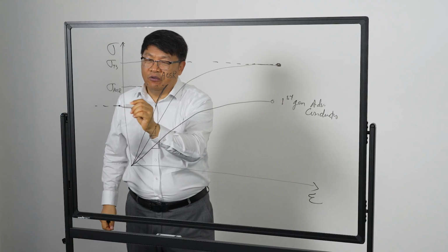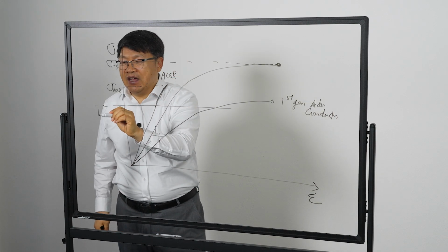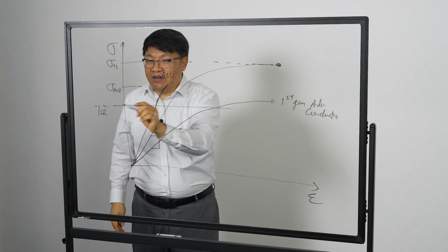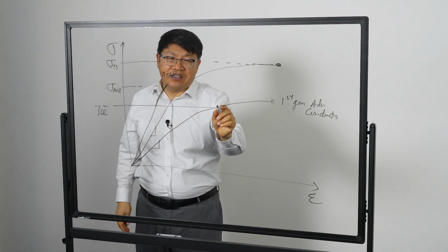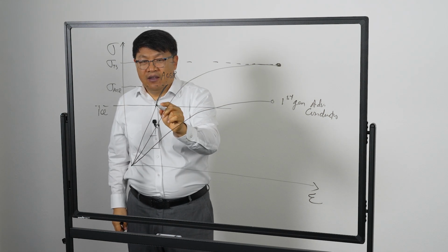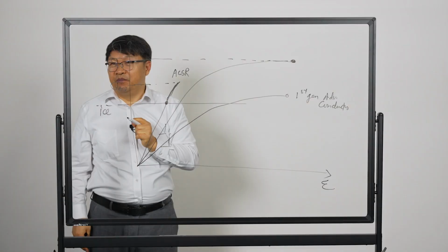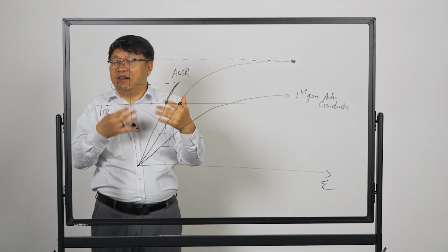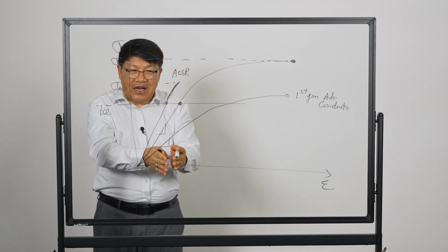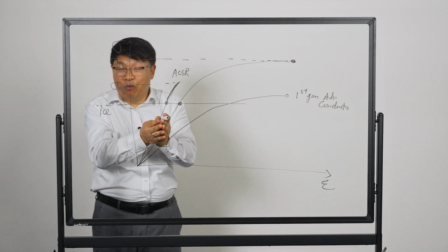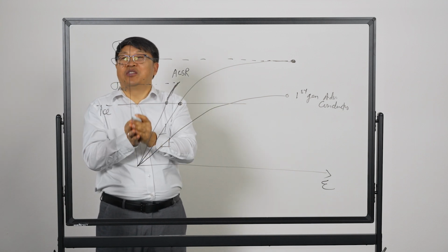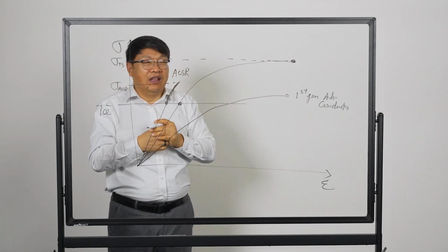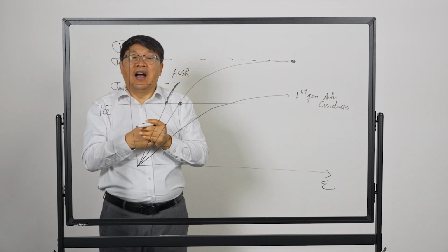So under certain ice conditions, which will drive the tension in the conductor, you look at how much these conductors might sag under the same tension. ACSR actually does pretty well because the steel has a pretty high stiffness. And the TS conductor does have a very decent modulus. So it will sag a little bit more compared to the conventional conductor. However, our overall sag is still substantially less than the sag in the traditional conductor, and that's why you are able to handle the ice load sag.